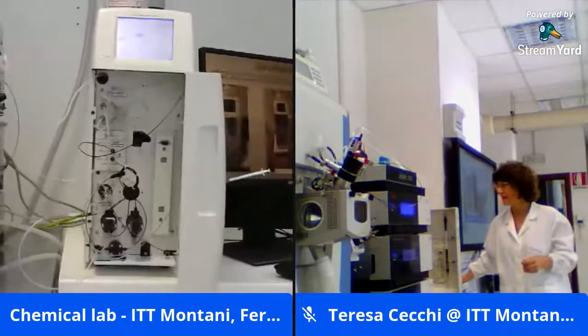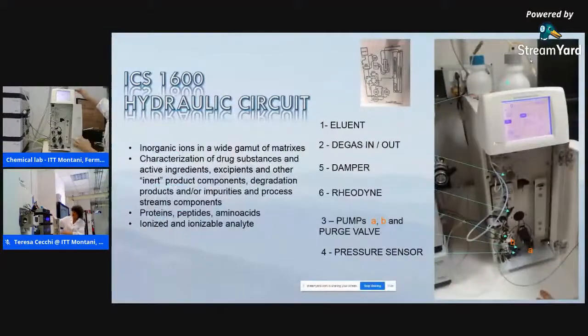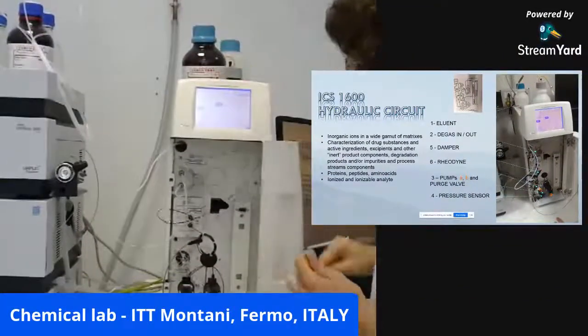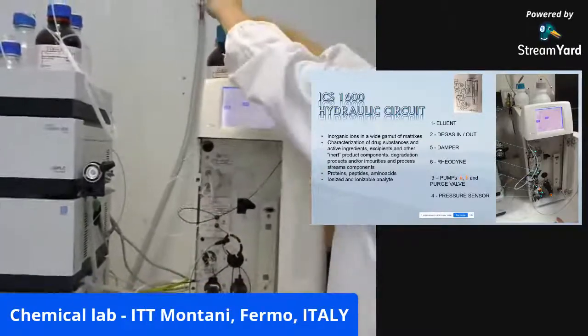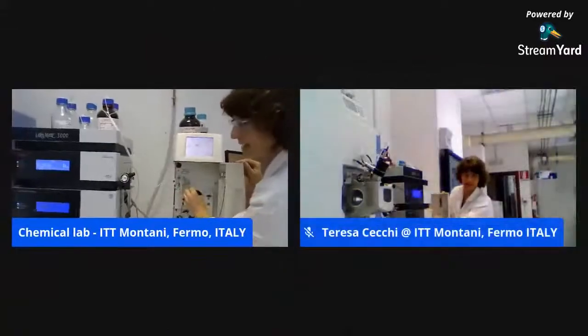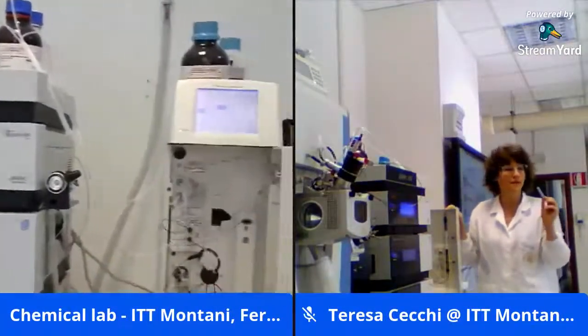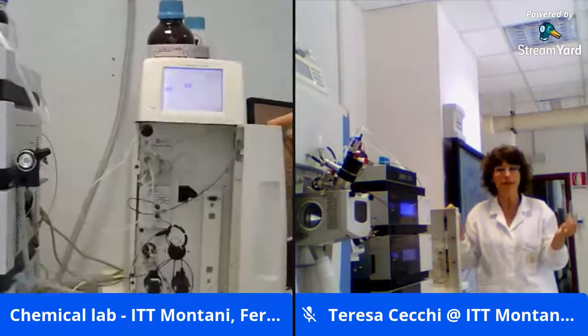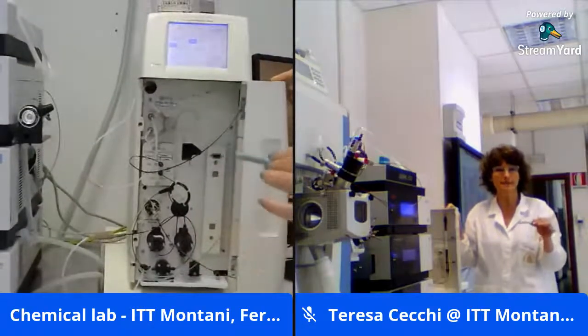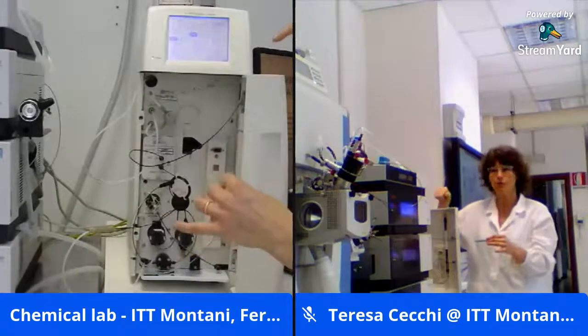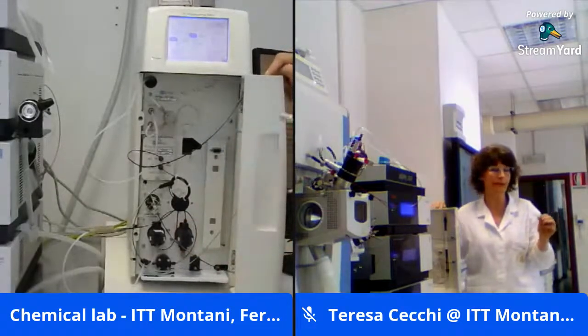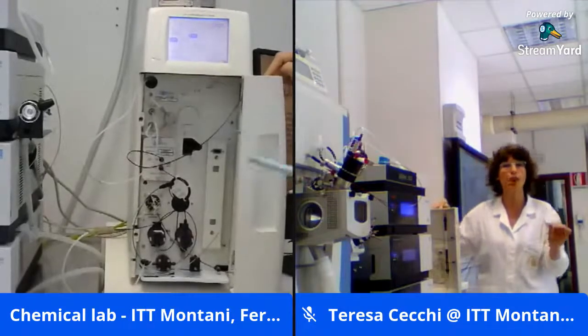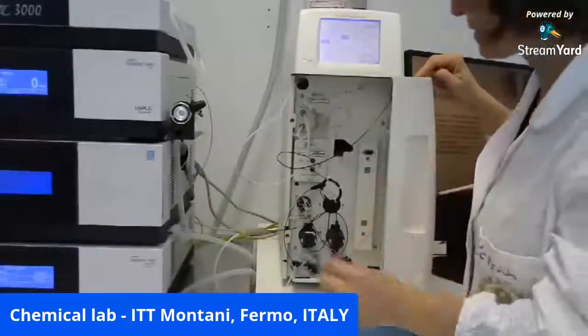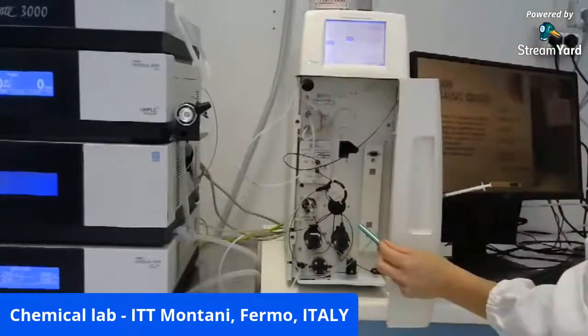Just a moment. Okay, here we go. Here you see the hydraulic circuit of the chromatograph, and the eluent from the bottle enters the degasser here. The degasser is crucial because dissolved gases would form a bubble in the detector, which is at the lowest pressure in the whole chromatographic hydraulic circuit. So bubbles are very detrimental, and we need to eliminate dissolved gases to prevent bubble formation. The degasser here is actually a membrane pump which will suck out dissolved gases from the solution.